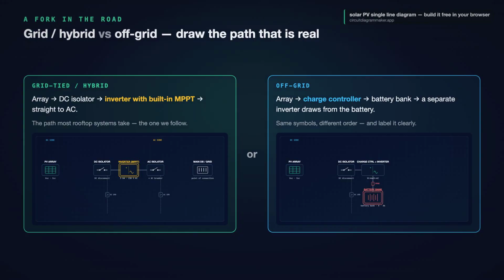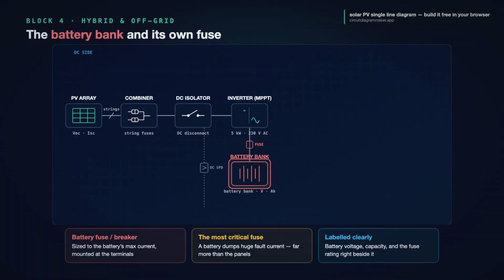Block 4, for hybrid and off-grid systems, the battery bank. The battery hangs off the DC bus, and between the battery and everything else sits its own protection, a battery fuse or a DC breaker, sized to the battery's maximum current, mounted as close to the battery terminals as you can get it. This is the most important fuse in the whole system, and here's why. A battery can dump enormous fault current, far more than the panels ever will. If a cable shorts, that fuse is the only thing standing between a fault and a fire.